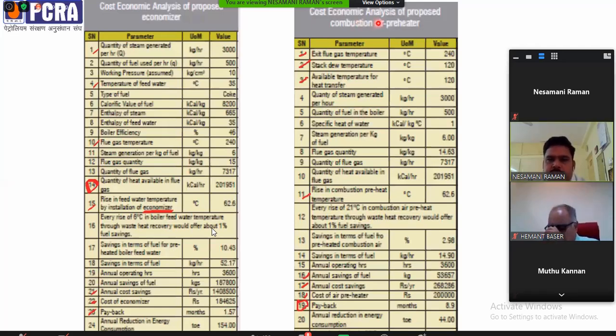Second is the air preheater. The flue gas temperature was 240 and the sulfur dew point temperature 120. Considering that, they could reduce the stack temperature, so that they could achieve an air temperature of almost 62 degrees Celsius. It resulted in a cost saving of almost 2.68 lakhs per year. The cost of the air preheater is 2 lakh. So payback was less than a year, 8.9 months only.